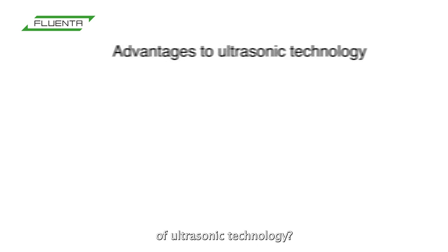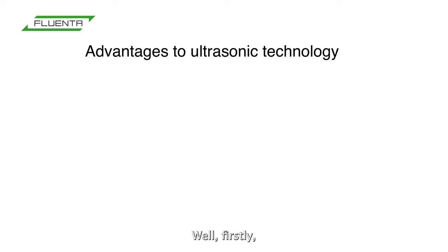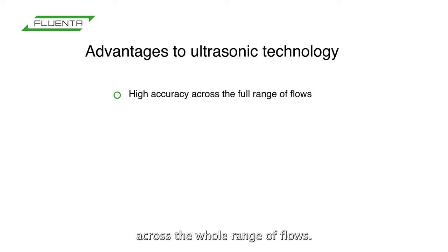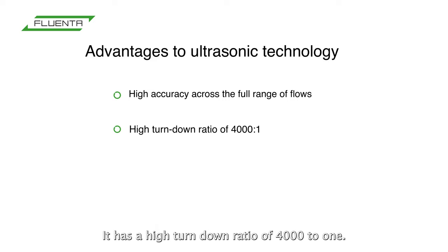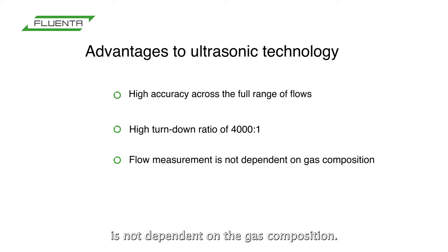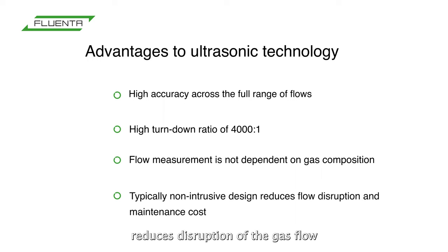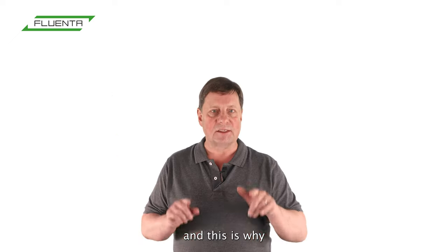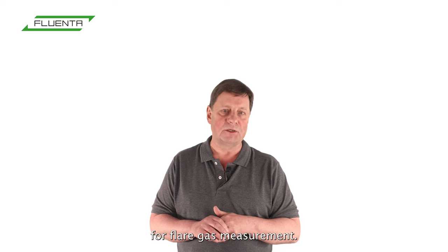What are the main advantages of ultrasonic technology? Well, firstly, it gives a high accuracy across the whole range of flows. It has a high turndown ratio of 4000 to 1. Importantly, the flow measurement is not dependent on the gas composition. And finally, the typically non-intrusive nature reduces the disruption of the gas flow and also reduces maintenance costs. And this is why ultrasonics is the technology of choice for flare gas measurement.